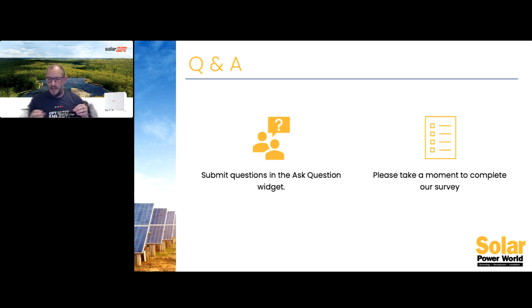That number is relatively small in the beginning. It depends on a lot of factors, like system size and the undulation or angulation of the terrain, which can also significantly impact energy production. But the number grows because the difference between the highest performing cell and the lowest performing cell widens over time, and we're able to capture what would otherwise be lost due to the averaging effect of the maximum power point tracking algorithm in a string inverter.